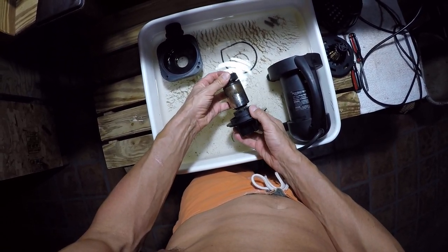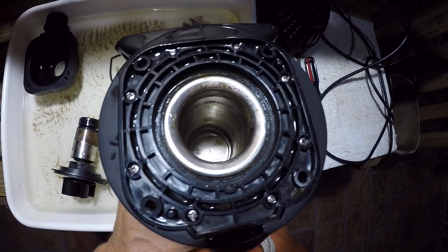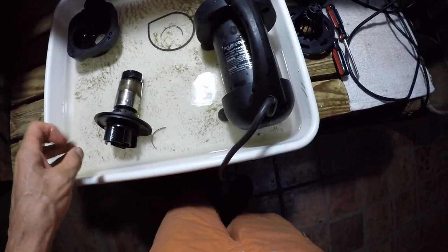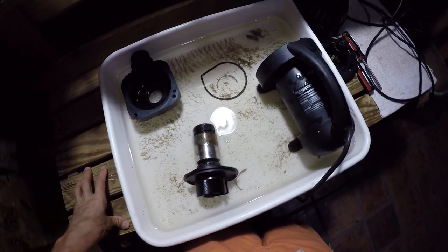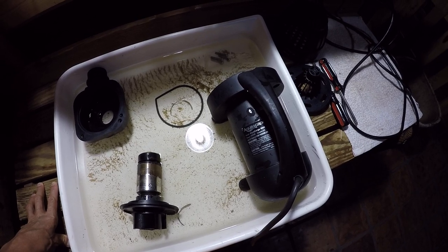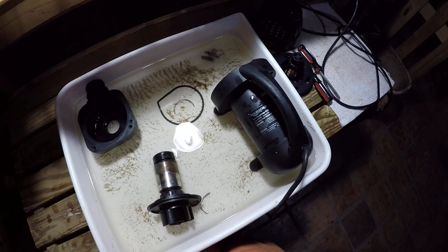Of course, that's the way it sits inside. Anyhow, this is toast — I'm pretty sure the cavity is also damaged. I could just replace the support and the impeller assembly, but from so much rubbing and heating I'm pretty sure the inside of the pump is toast also. It's a good pump. We bought them about ten years ago — it was a great deal, about $280 each for 20 pumps. Back then the normal price was about $350, and today it's like $450–$500 for these pumps.